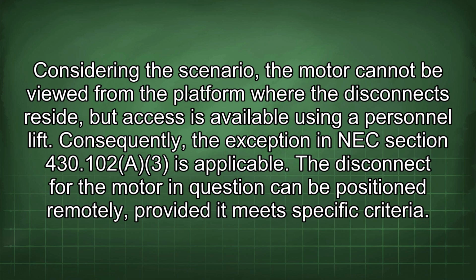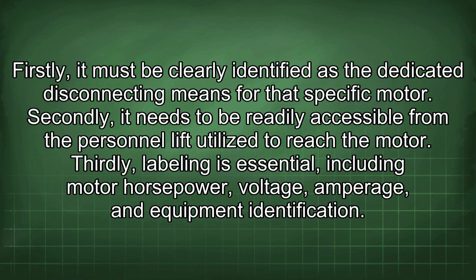Consequently, the exception in NEC Section 430.102(A)(3) is applicable. The disconnect for the motor in question can be positioned remotely provided it meets specific criteria. Firstly, it must be clearly identified as the dedicated disconnecting means for that specific motor. Secondly, it needs to be readily accessible from the personnel lift utilized to reach the motor. Thirdly, labeling is essential, including motor horsepower, voltage, amperage, and equipment identification.